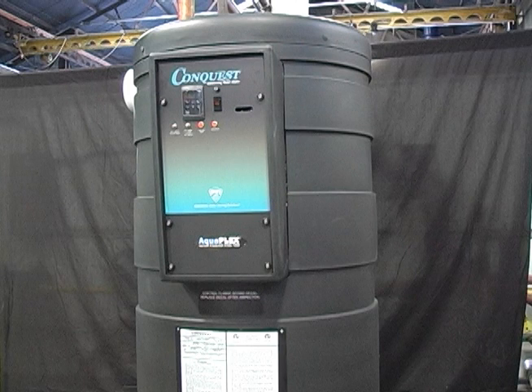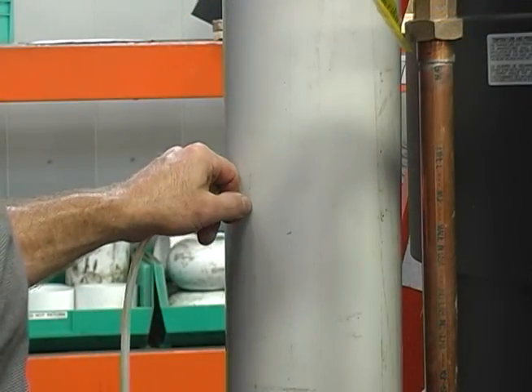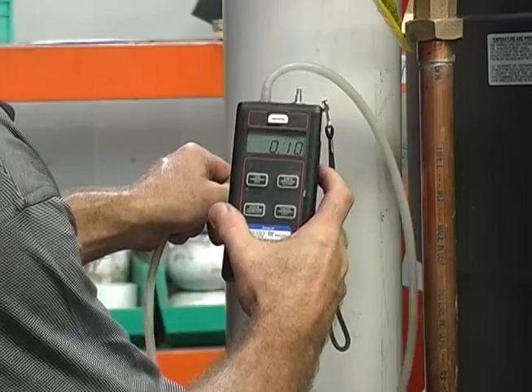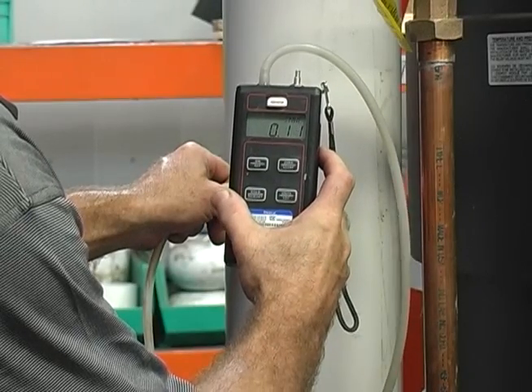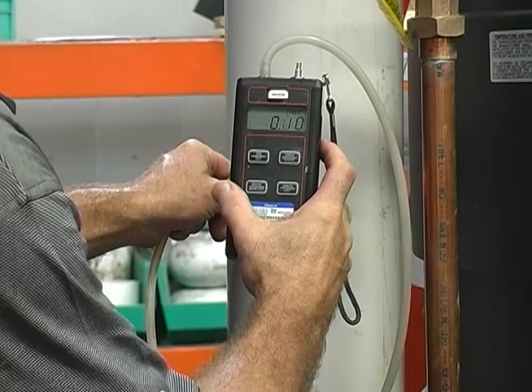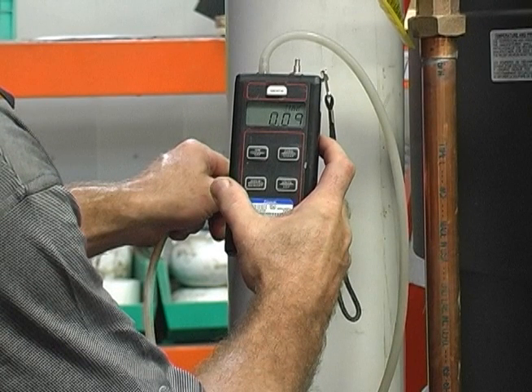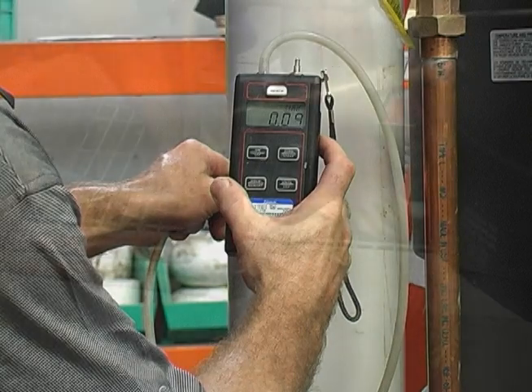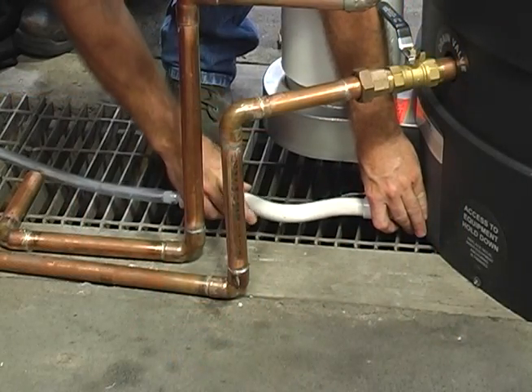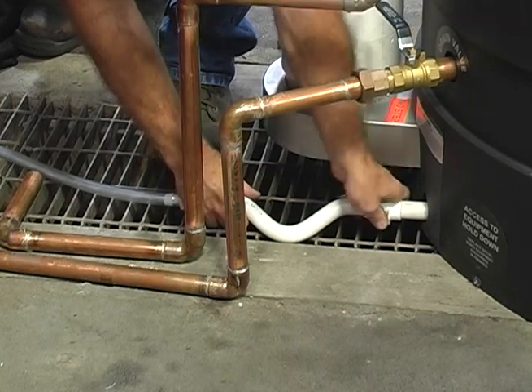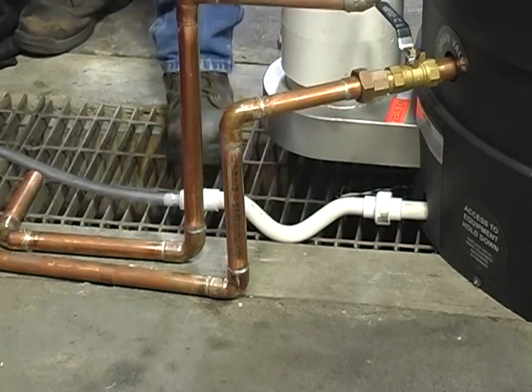With combustion setup complete, there are only a few remaining items to check before startup is done. Using the same vent opening that was used for combustion adjustment, measure the vent pressure. When the water heater is at high fire, confirm the vent pressure does not exceed 1/2 inch water column. Pressure in excess of 1/2 inch indicates a venting sizing issue that must be addressed by the installer before operating the water heater. Check to confirm the condensate trap is rotated to its lowest position as shown in the installation and maintenance manual.